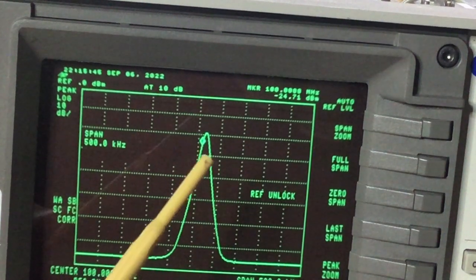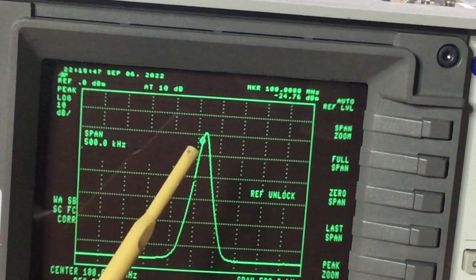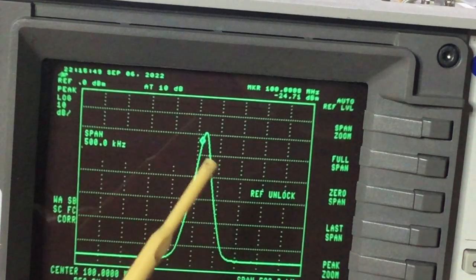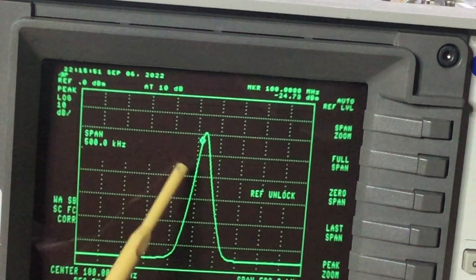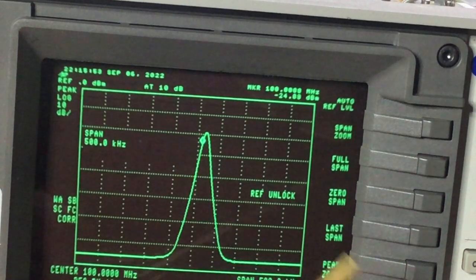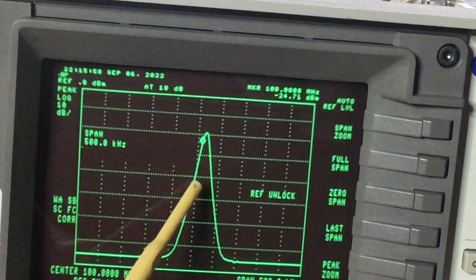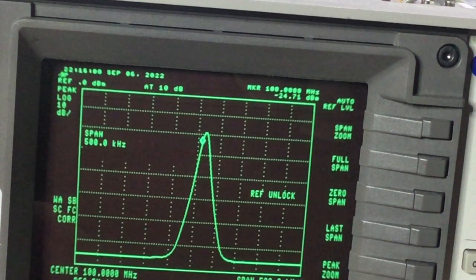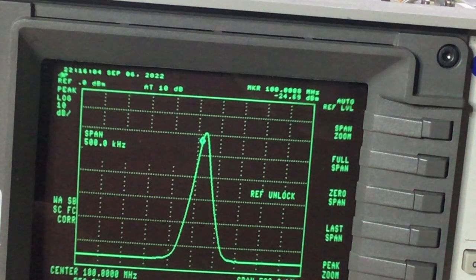I think when we first started this repair, it was 10 megahertz off frequency at least, and that was on a good day. So for it to remain as stable as it is, at 500 kilohertz bandwidth, it's still a little off frequency, and we might be able to do some more adjustments. And then once we get it close enough, we can do a calibration.